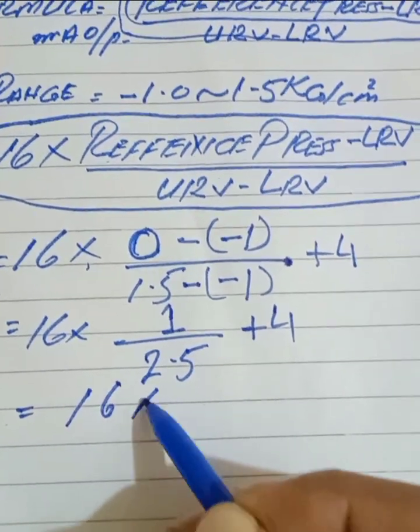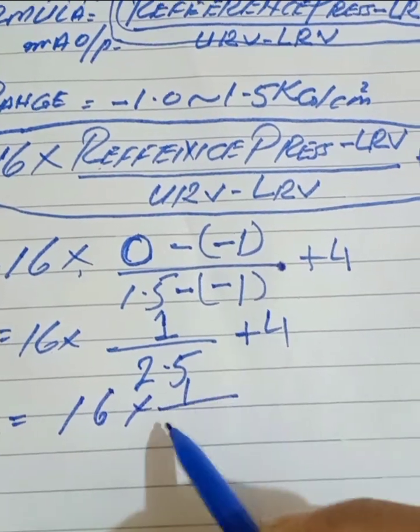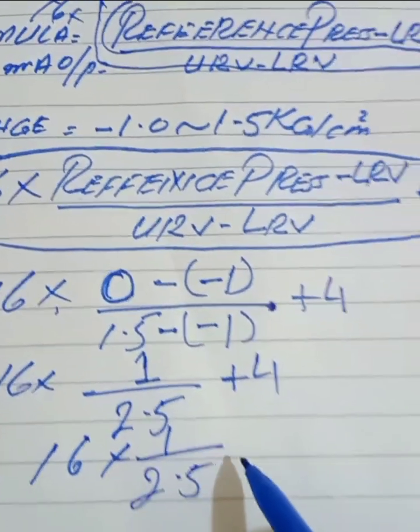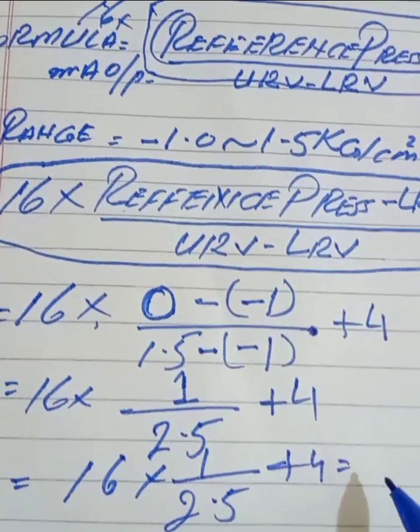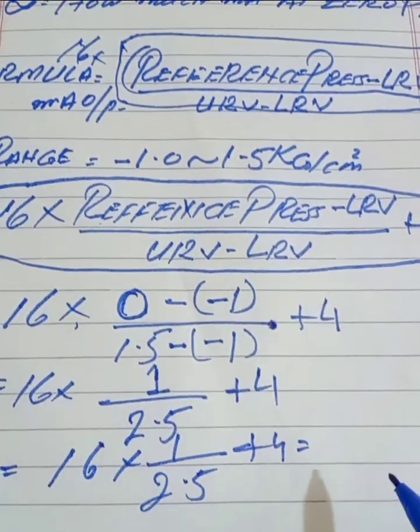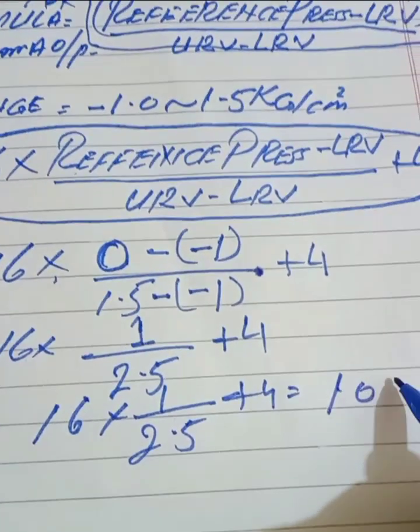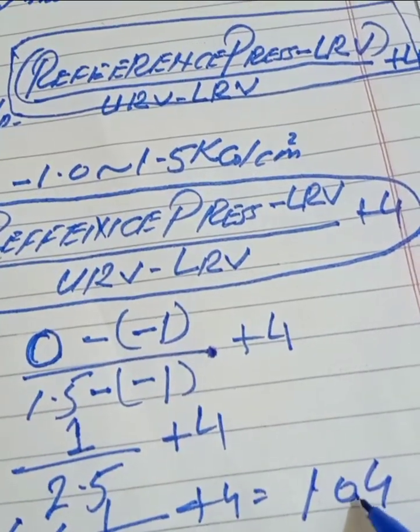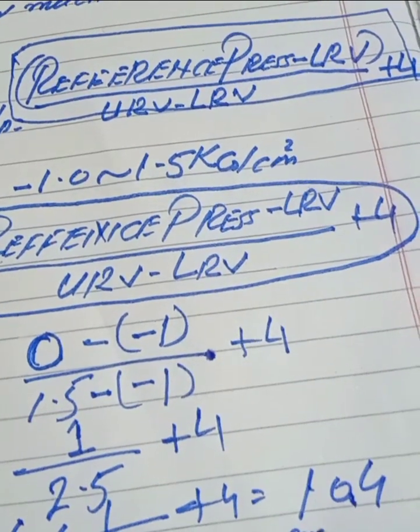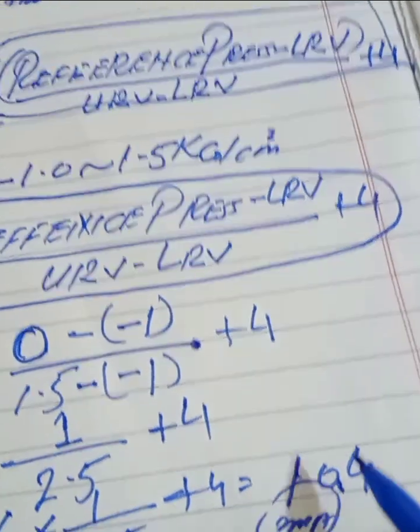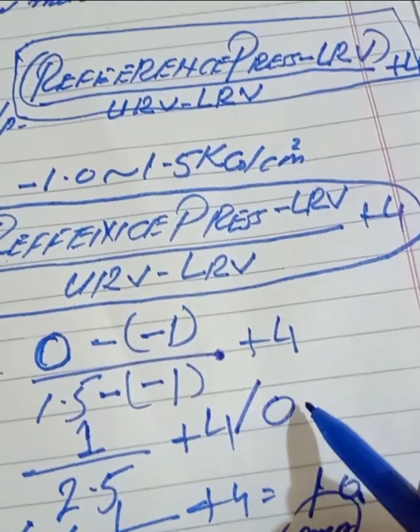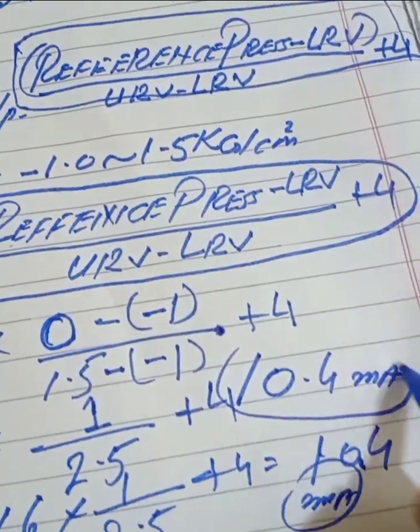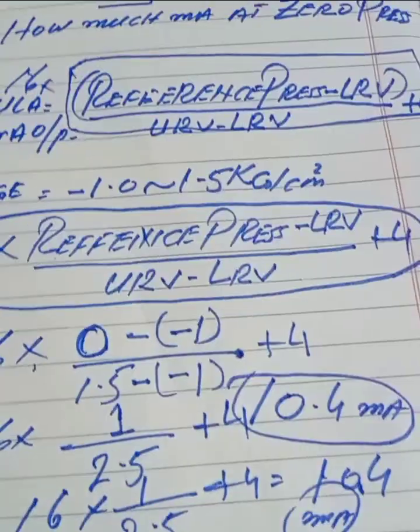So the result is: 16 into (1 over 2.5) plus 4, which gives us 10.4 milliamps. The answer is 10.4 milliamps. This is our transmitter output at zero pressure.